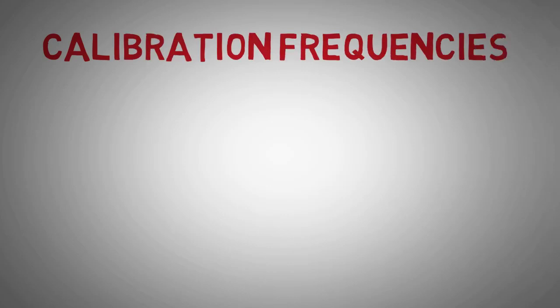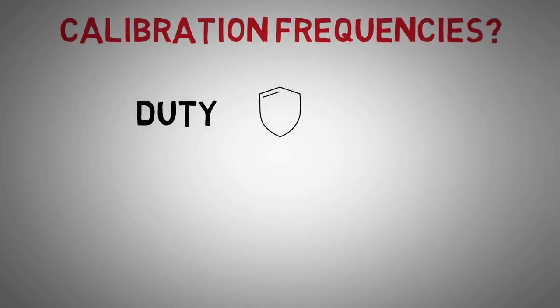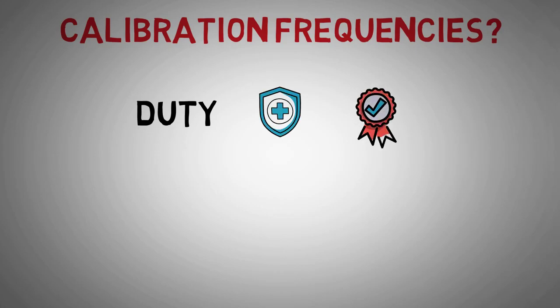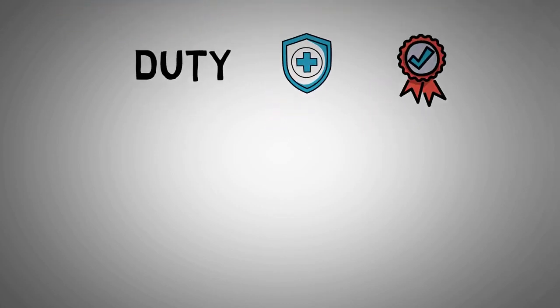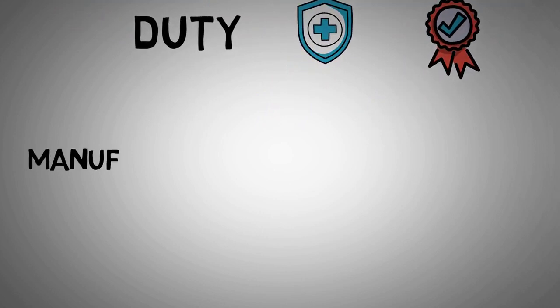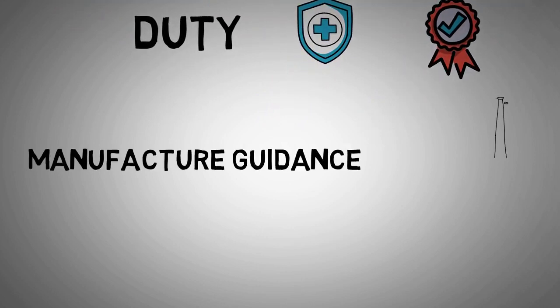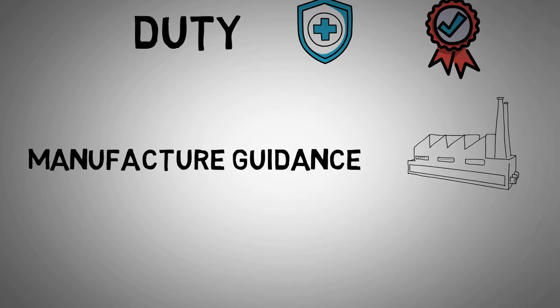So, what determines how often we calibrate an instrument? Duty. If a transmitter's accuracy is safety and quality critical, it might be calibrated monthly. If it is just giving supplementary information, it might be only calibrated every 2 years. Manufacturer guidance. It can also be dependent on the transmitter type, and the manufacturer will provide a recommended calibration period in its literature. Standards.